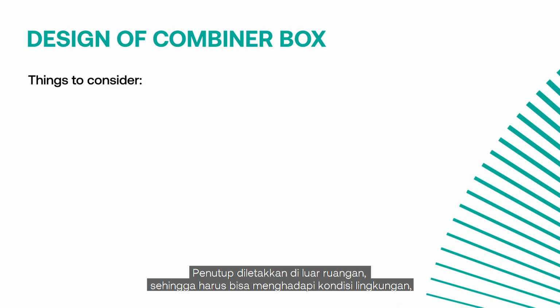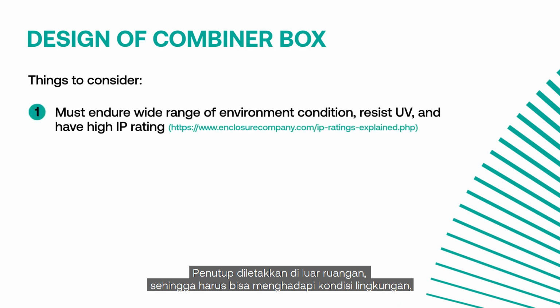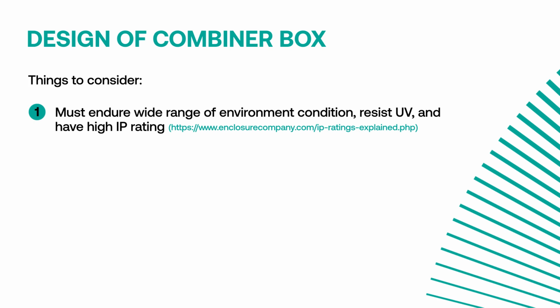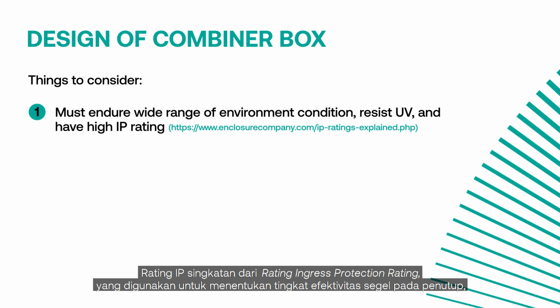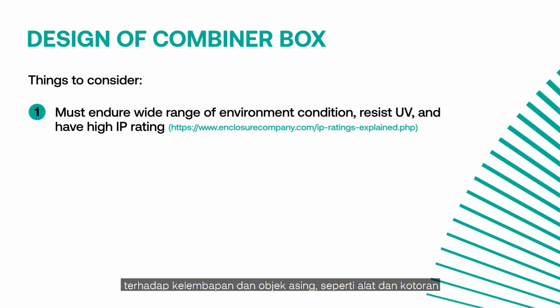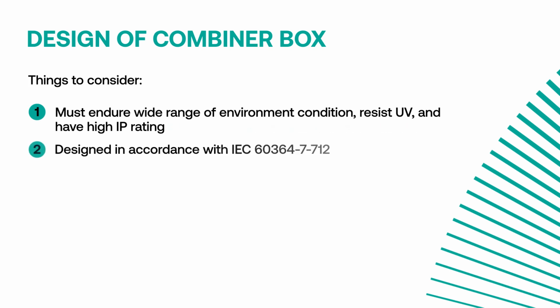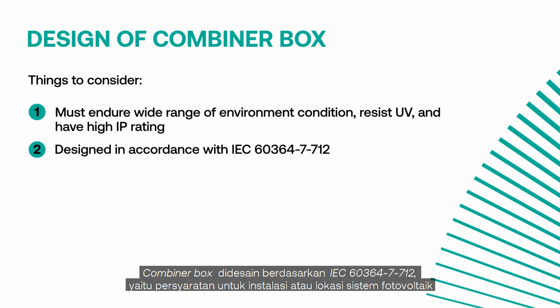When designing a combiner box, you should consider the following. The enclosure is located outdoors, thus it must endure a wide range of environmental conditions, resist UV, and have a high IP rating to avoid water and small object intrusion. IP rating stands for Ingress Protection Rating, which is used to define the level of sealing effectiveness of an electrical enclosure against intrusion from moisture and foreign objects, such as tools and dirt. A combiner box is designed in accordance with IEC 60364-7-712, that is, requirements for special installations or locations.